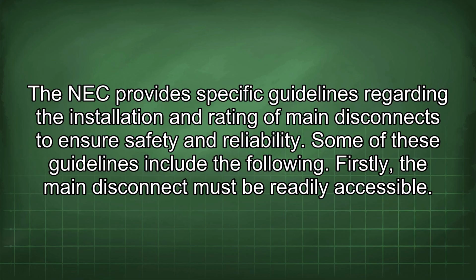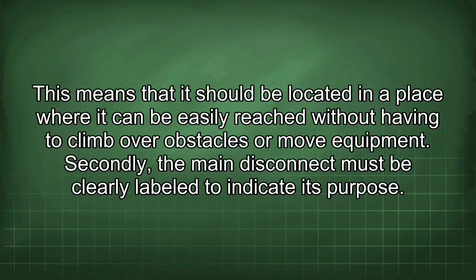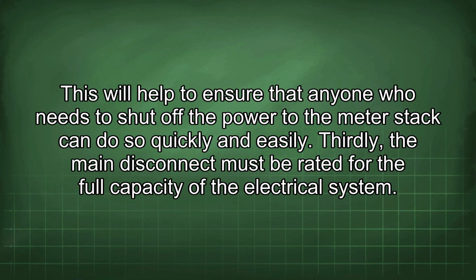Firstly, the main disconnect must be readily accessible. This means that it should be located in a place where it can be easily reached without having to climb over obstacles or move equipment. Secondly, the main disconnect must be clearly labeled to indicate its purpose. This will help to ensure that anyone who needs to shut off the power to the meter stack can do so quickly and easily. Thirdly, the main disconnect must be rated for the full capacity of the electrical system.